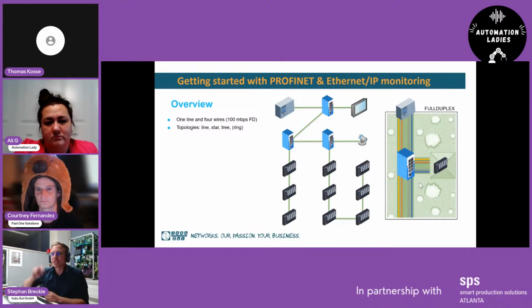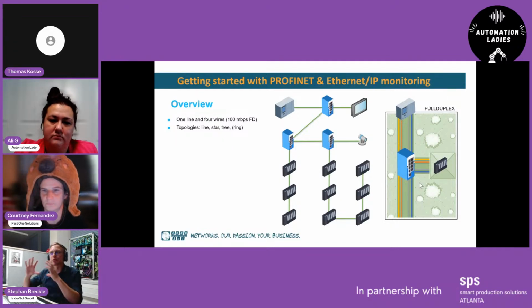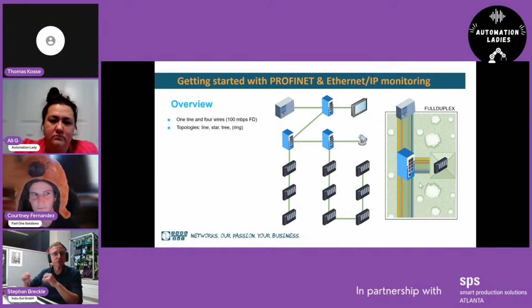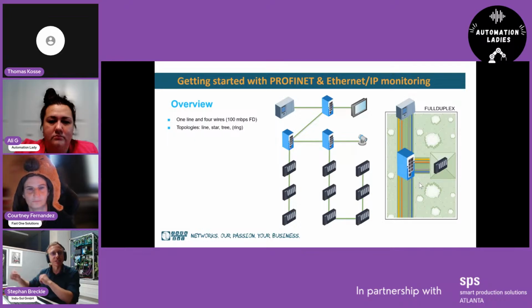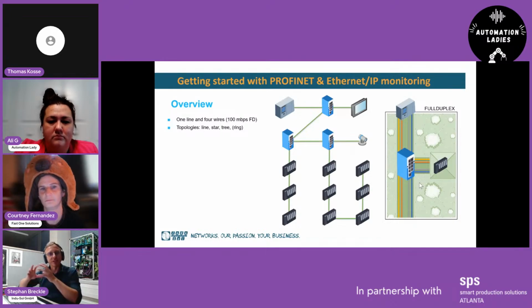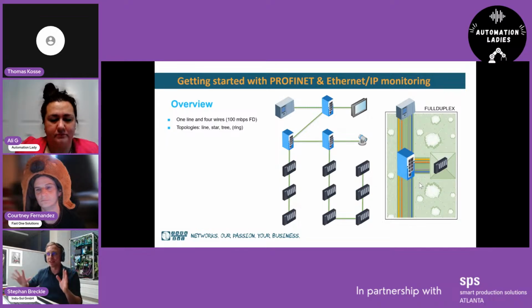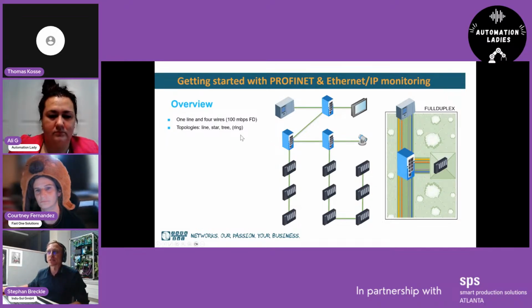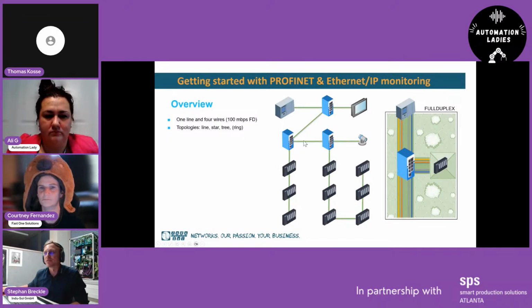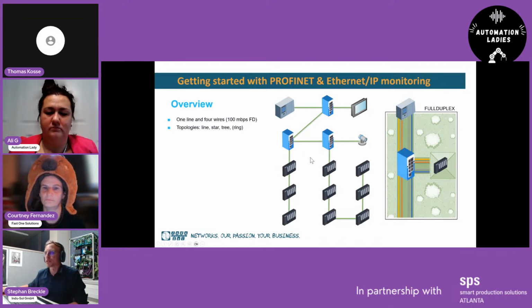Just a hint - this is why I put ring topology in brackets. For ring topology you need a special protocol - in PROFINET it's MRP, Media Redundancy Protocol, and in Ethernet IP it's Device Level Ring - and the devices have to support it. If they support it, you can handle ring topology; if not, you cannot, and connecting a ring would stop your whole system. So be careful - only if your device supports the ring and the ring is configured can you handle this kind of topology.